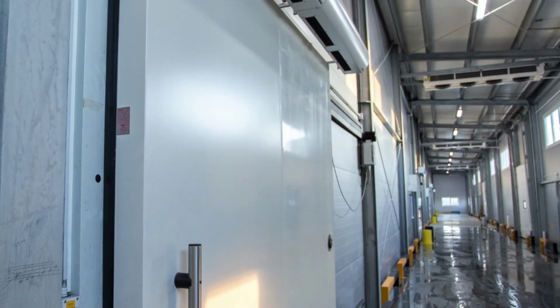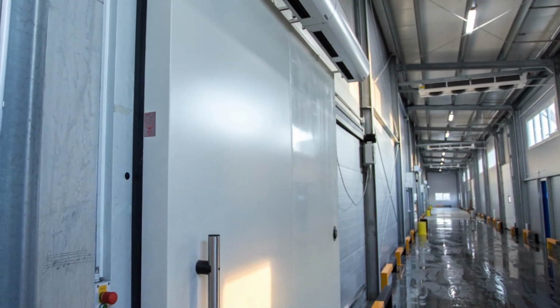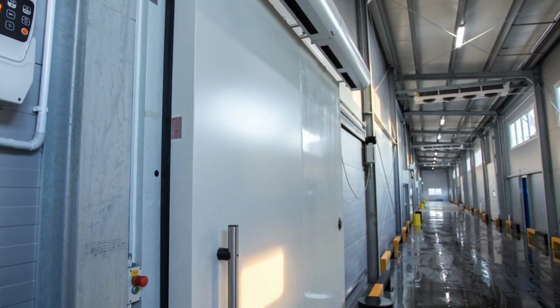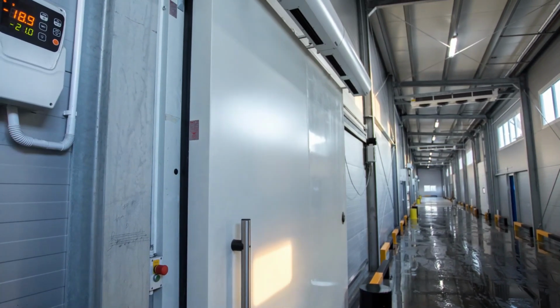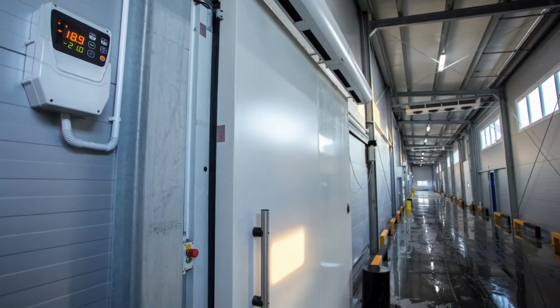Doors too, right? A lot of these systems have conveyance systems. They're moving through doors, but those doors might be between spaces that are at different temperatures. So we have to really think through door design and all of those conveyance doors in order to make sure that the different temperature zones are isolated and that we're not creating places where we're getting ice or water dripping or other things that can happen when you have two different temperature zones at these kind of temperatures competing against each other.